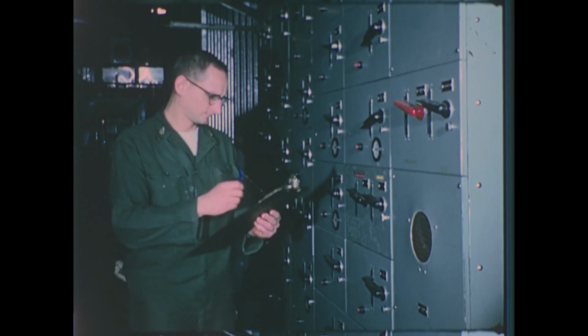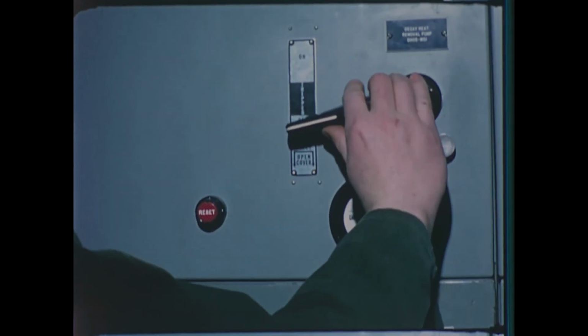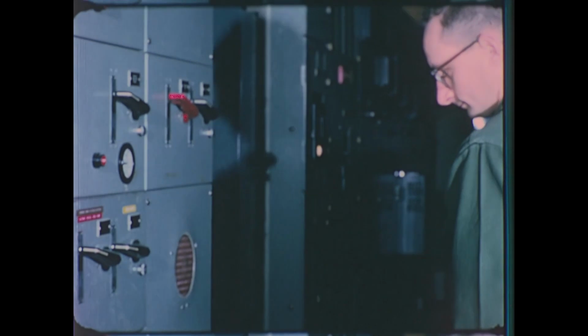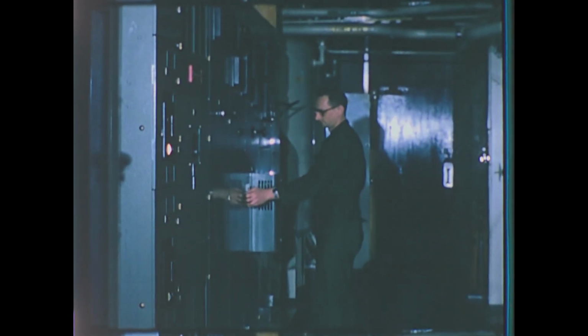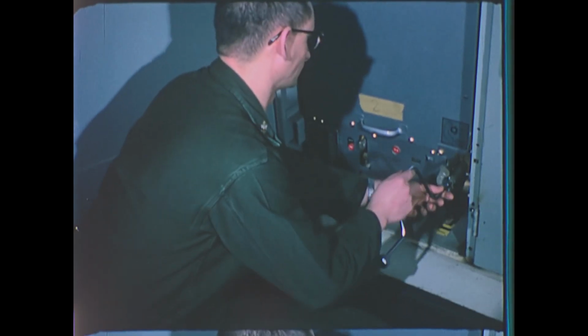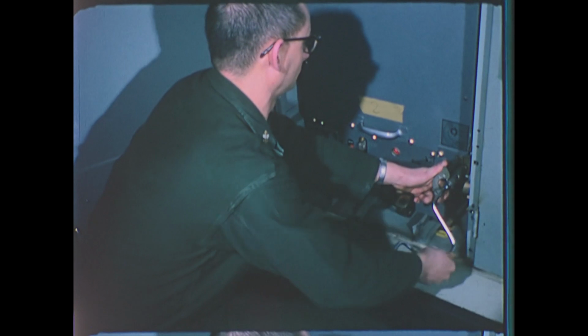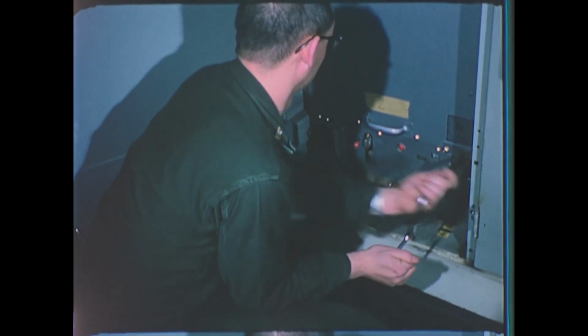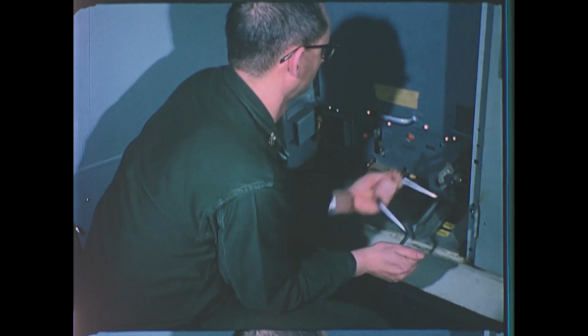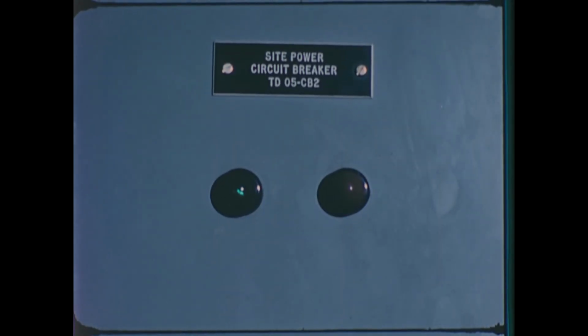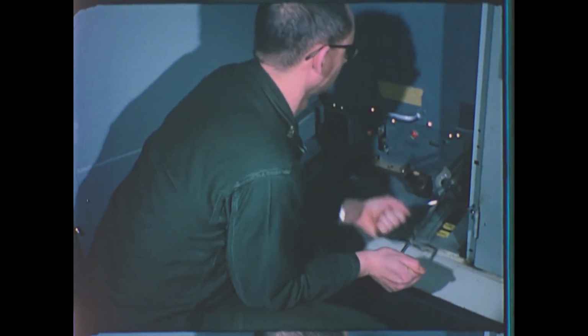During the normal 8-hour startup time, beginning with all primary plant systems normal and ready for operation, 3 checklists are followed. Here, with all electrical breakers properly lined up, the operator racks in the tie line breaker in the 4160-volt switchgear. This breaker is interchangeable with those used in the turbine generator and the station service transformer.